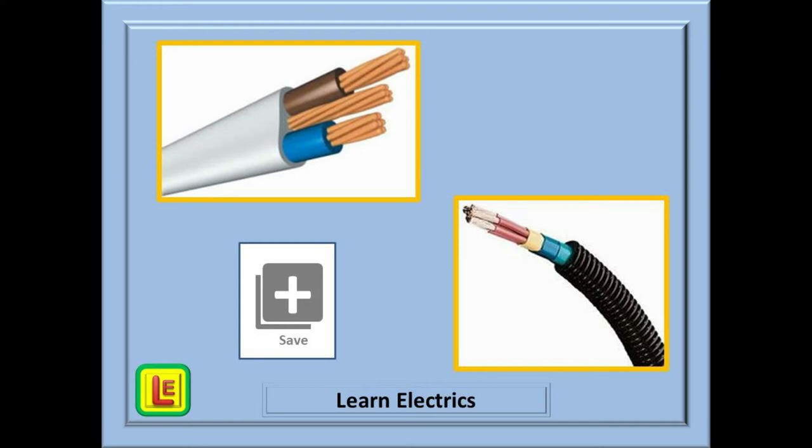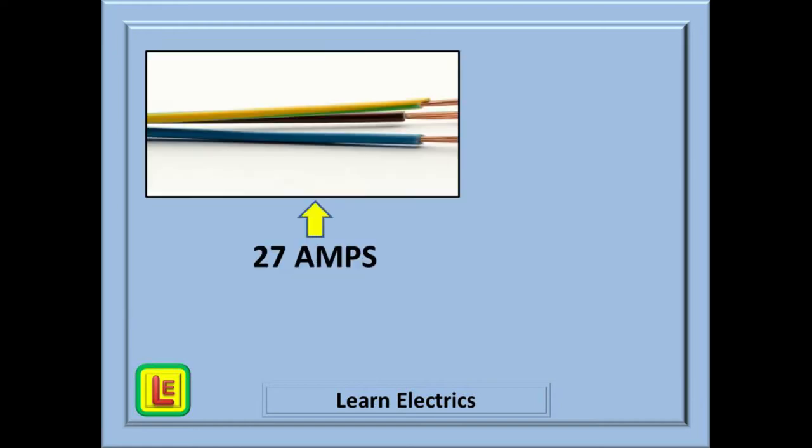And not just conduit inside walls, in brickwork, in the loft. Just about any location will affect the cable's ability to lose heat. And this is the purpose of the tables. Before we move on, you may want to press the save button at this stage. Also, if you are going to follow along with the wiring regulations book, this information is found in Appendix 4. I am using the blue 18th edition book for this video, and I am starting at page 386.